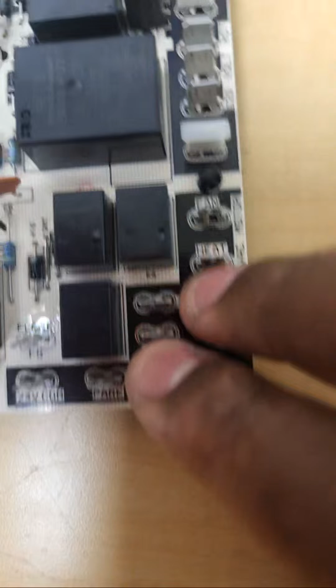And then lastly, what we have here are the park terminals. Park pretty much means, guys, that whatever's hooked up here is not going to be in use. Most blower motors, even though you only really need 2 speeds, cool and heat, in this case you have 3: your continuous fan terminal, your heat terminal, and your cool terminal. But it's not uncommon for blower motors to have at least 5 or 6 different speeds. For those extra speeds that you probably don't need, instead of cutting them and wire nutting them or zip tying them, you can actually hook those terminals up. These are unused taps here. So remember, guys, park means it's not in use.